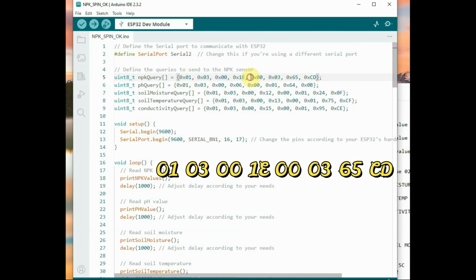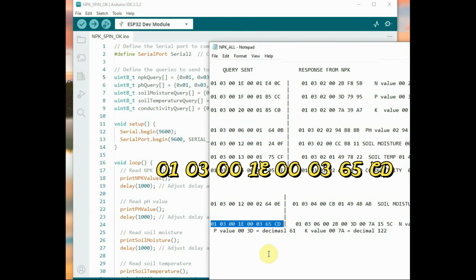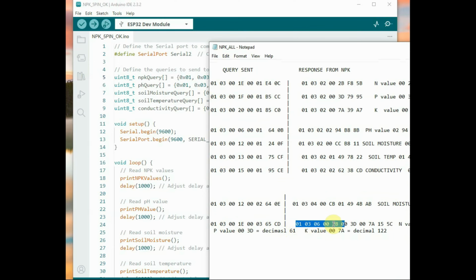01 is the address, 03 is the function code for read register, 001E is the start address, and 0003 is the number of registers. Finally, 65CD is the CRC code. This is very important; if the CRC is wrong, you will not get the data back.